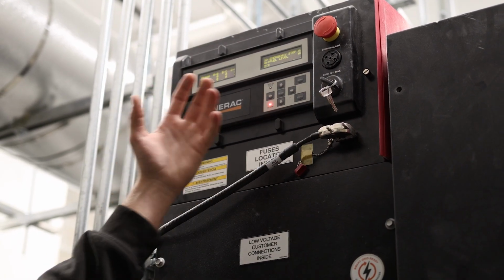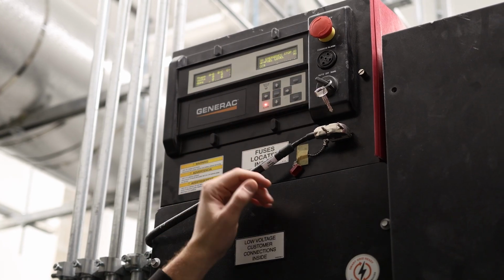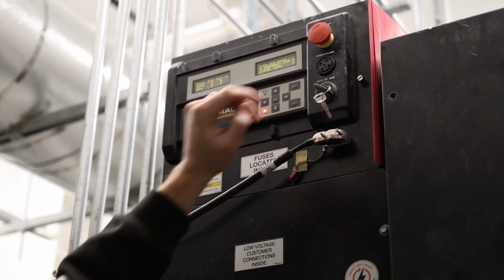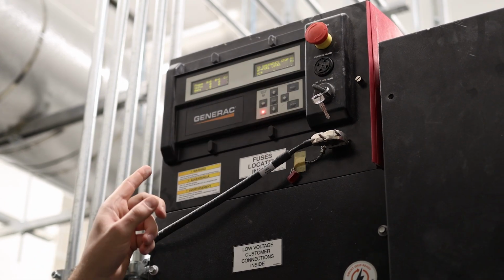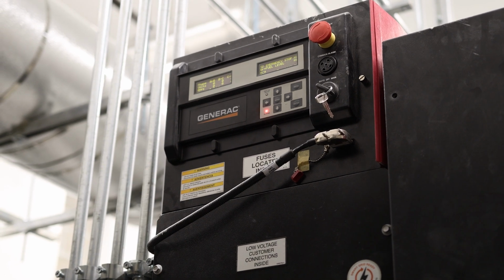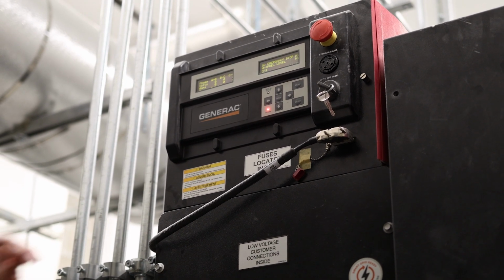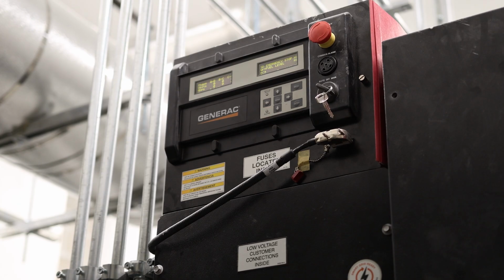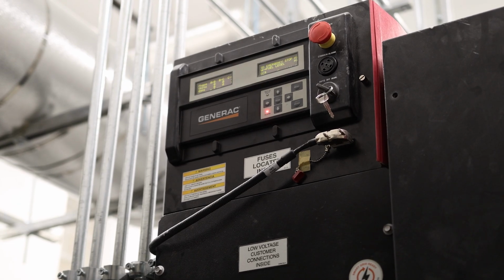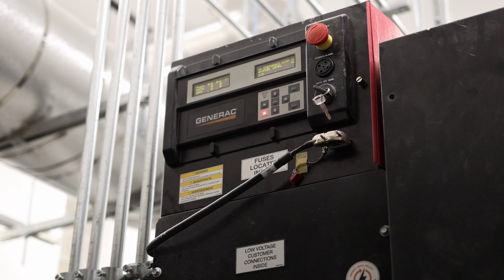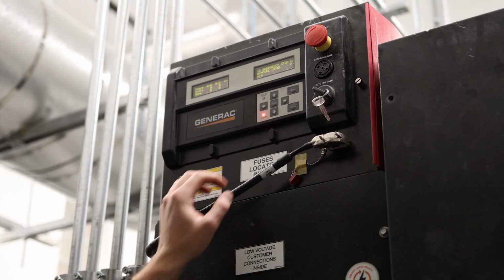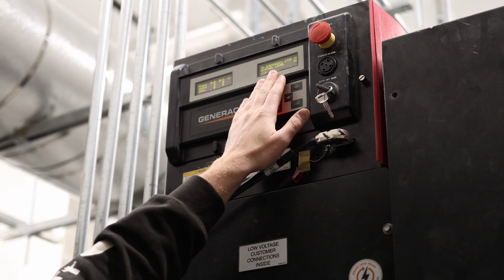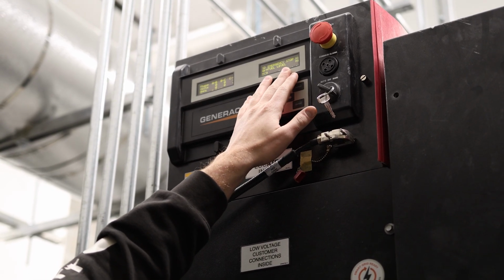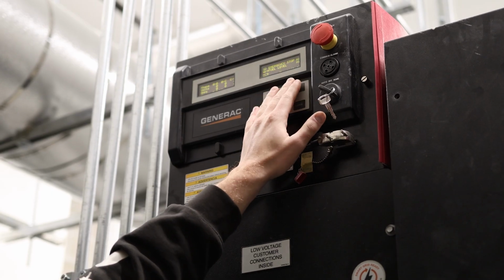The unit will annunciate through its own buzzer, as well as the annunciator inside will buzz, as well as your fire alarm panel will buzz. You're going to notice that if the generator throws an alarm, it's going to be someone calling you. So it'll now show the most current alarm that happened at the top, shutdown emergency stop.